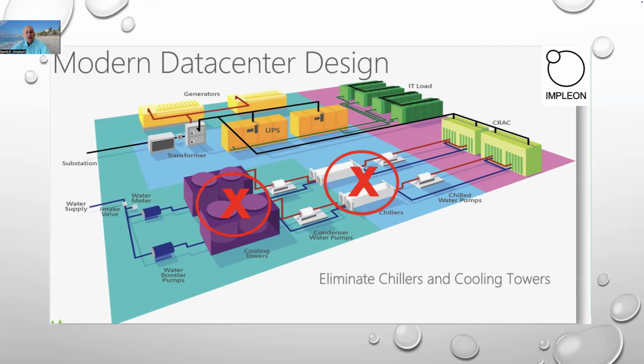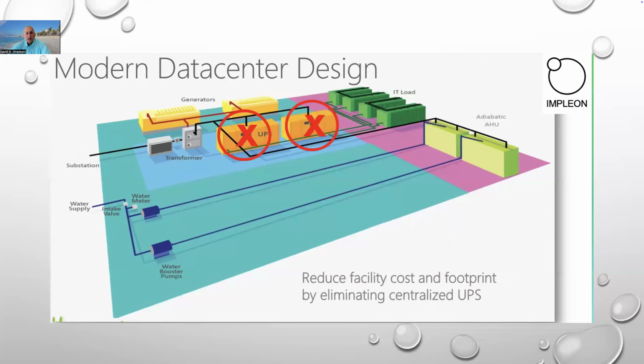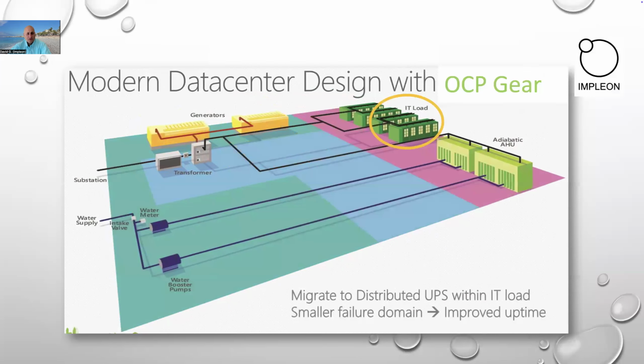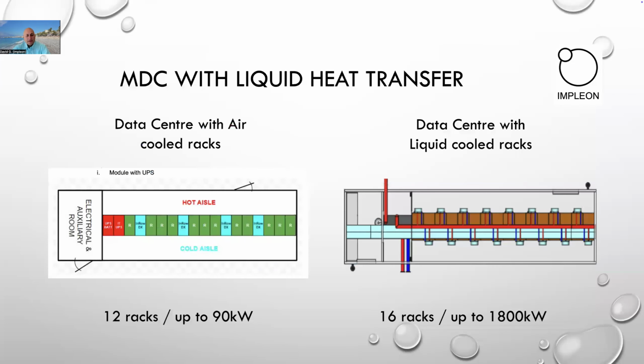This is the traditional data center design. If we shift to OCP racks, we can have much higher inlet air temperature, which allows us to take away chillers and cooling towers. Also, we can have on rack level a power shelf with a battery shelf, which allows us to take away centralized UPSs. And overall, the power input for the data center is reduced, and that may also impact the gensets, which provide the overall energy for the data center. This is the way of decarbonization on facility level.